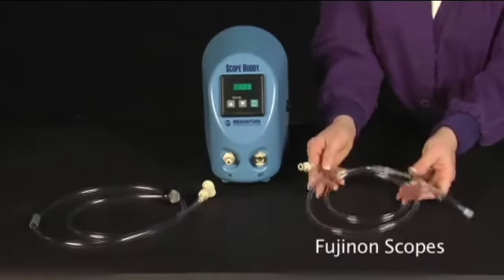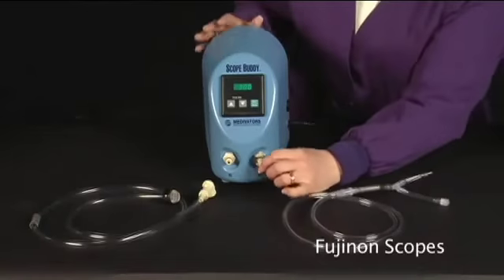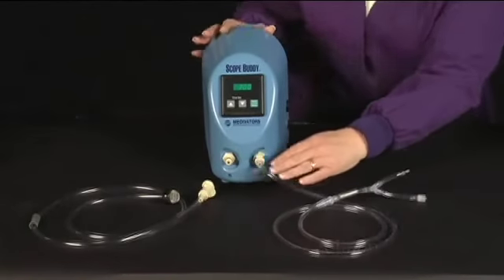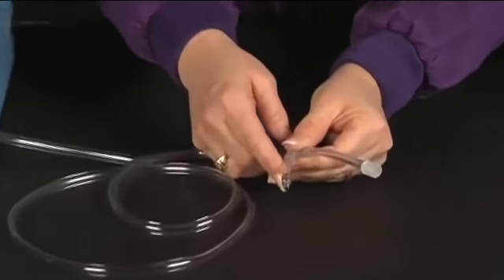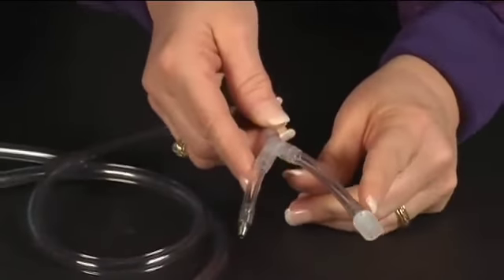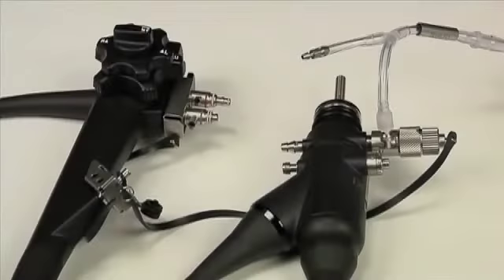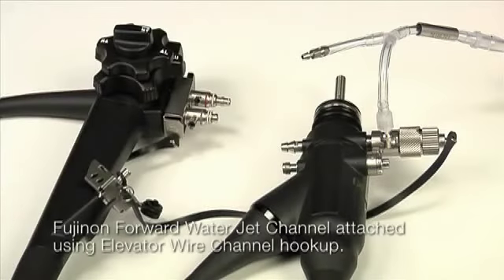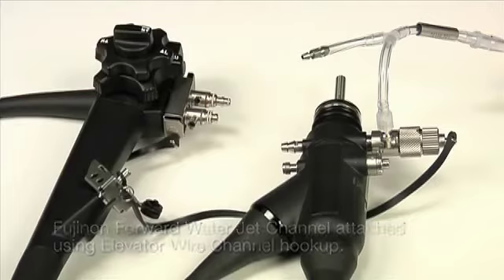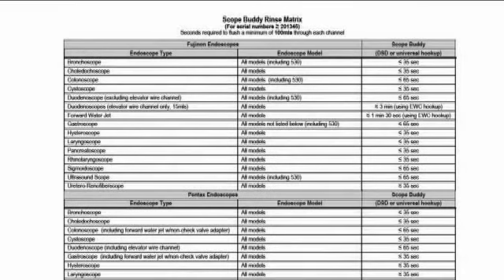Then, remove the universal cleaning adapter extension line and snap the elevator wire channel hookups into the port labeled out. The other end has a metal port that remains open, and the luer lock connector attaches to the endoscope's forward water jet or elevator wire channel, depending on which channel is being flushed. Reference the Scope Buddy rinse matrix to set Scope Buddy to the required time to flush the elevator wire channel of a Fujinon duodenoscope or the forward water jet channel of a Fujinon endoscope.